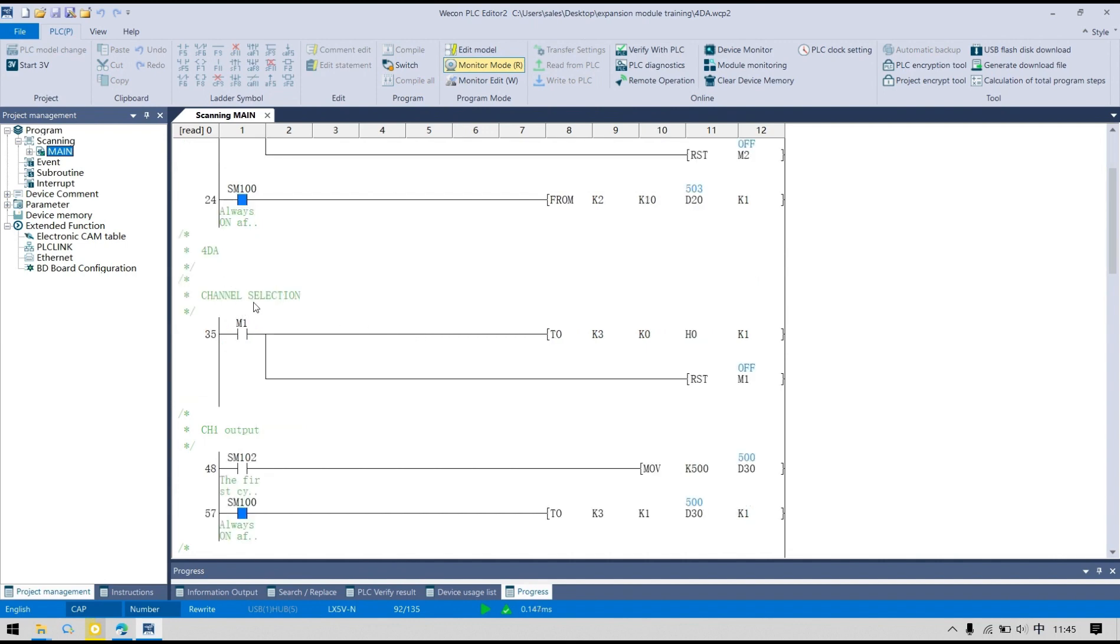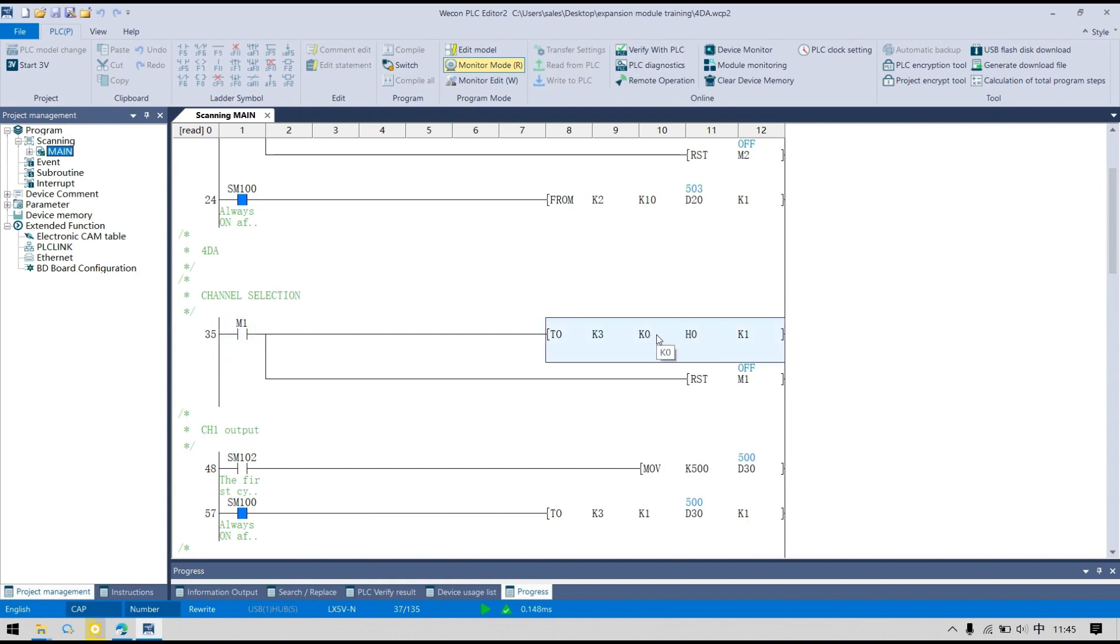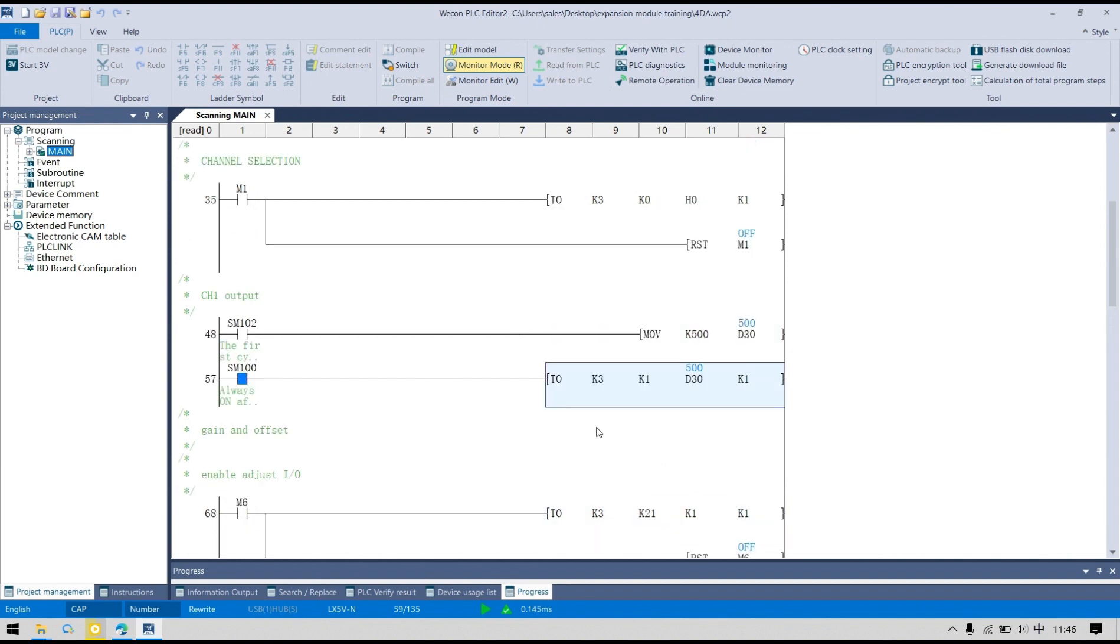First, we can see channel selection. I write H0 to BFM0, which means channels 1 to 4 are all minus 10 to 10V output. In this position, I use channel 1 to provide an analog output.